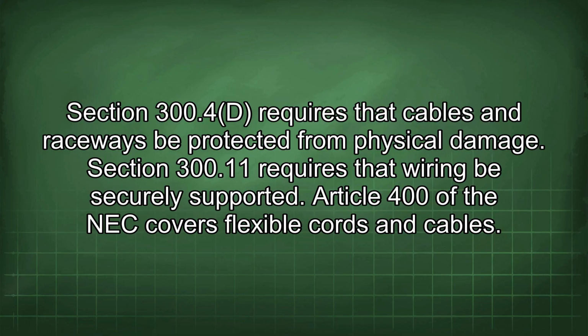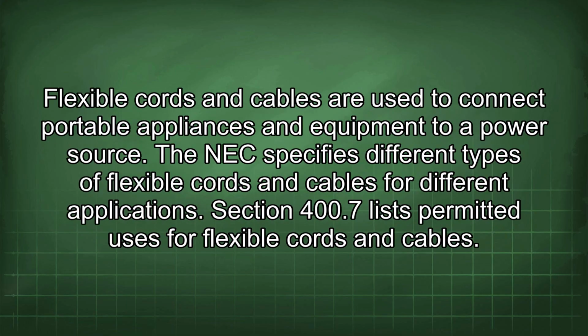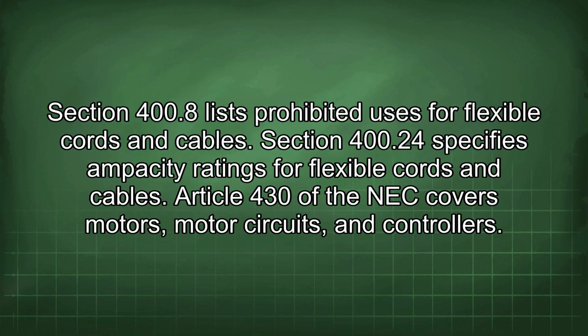Article 400 of the NEC covers flexible cords and cables. Flexible cords and cables are used to connect portable appliances and equipment to a power source. The NEC specifies different types of flexible cords and cables for different applications. Section 400.7 lists permitted uses for flexible cords and cables. Section 400.8 lists prohibited uses for flexible cords and cables. Section 400.24 specifies ampacity ratings for flexible cords and cables.